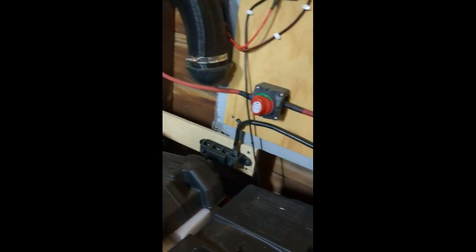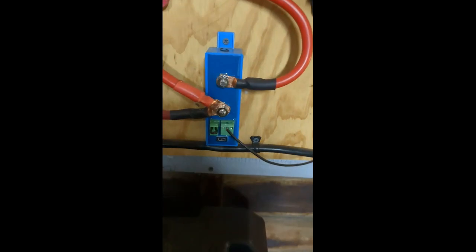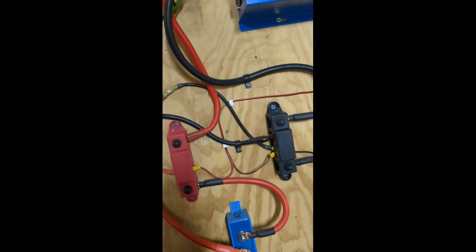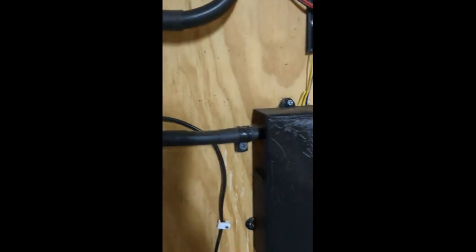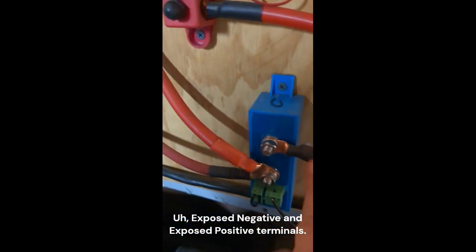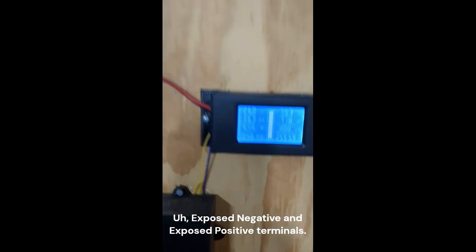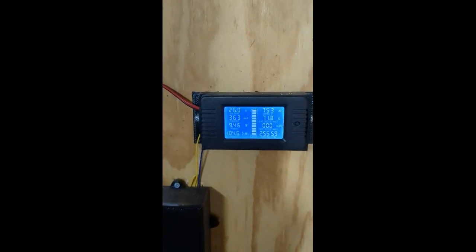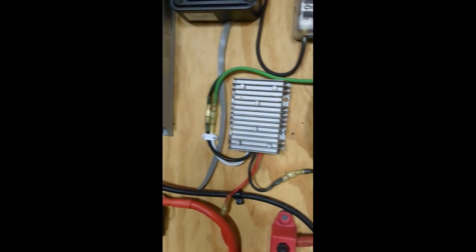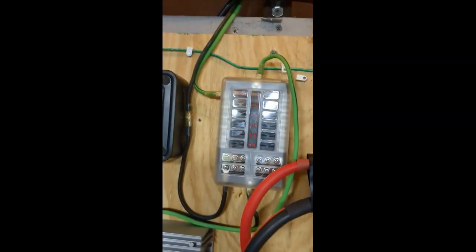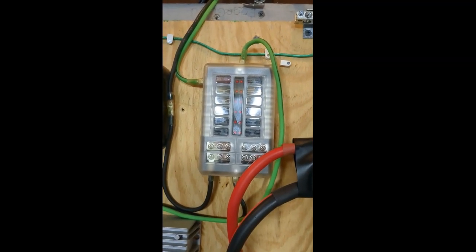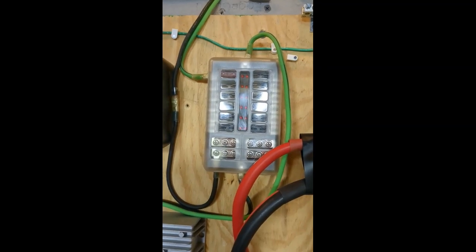The shelves themselves are tied to ground and that goes to my ground rod outside. Of course you want fire protection, smoke detector, I got CO2 over there. Out of the battery I come back, I got my Victron low power cutoff to protect the batteries, I've got another set of posts, this is a battery shunt. I just put a little 3D printed cover over it so that I didn't ever have an open ground and an open positive. That goes to my little monitor here, up to my 24 volt to 12 volt converter, to my 12 volt power panel.